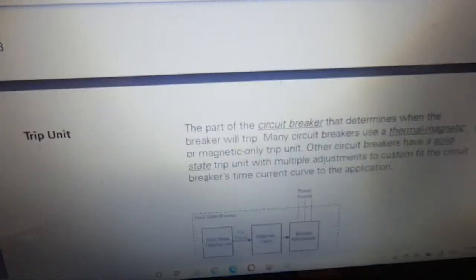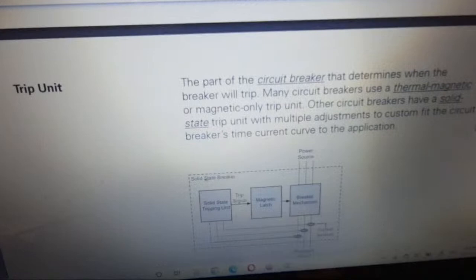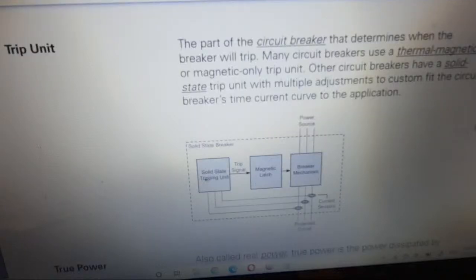Trip unit, a part of the circuit breaker that determines when the breaker will trip. Many circuit breakers use a thermal magnetic or magnetic only trip unit. Other circuit breakers have a solid state trip unit with multiple adjustments to custom fit the circuit breaker time current curve to the application.